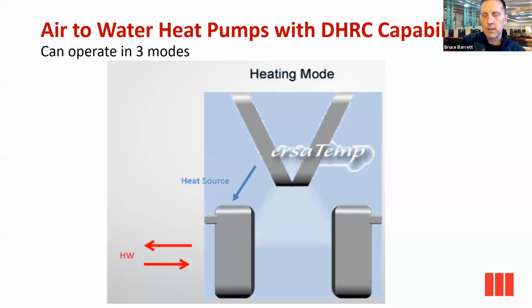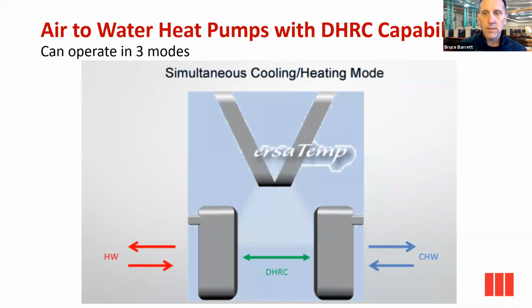Third mode, really not using the coil. We're using it as a water-to-water heat pump that we've talked about earlier. It's 4 pipes, 2 pumps. We're not using the coil at all. It is a strict water-to-water heat recovery chiller. Pretty simple concept. Our controller takes over 4 valves to direct where refrigerant is going. There's ball valves in there, so it positively isolates refrigerant going to the coil in this instance.